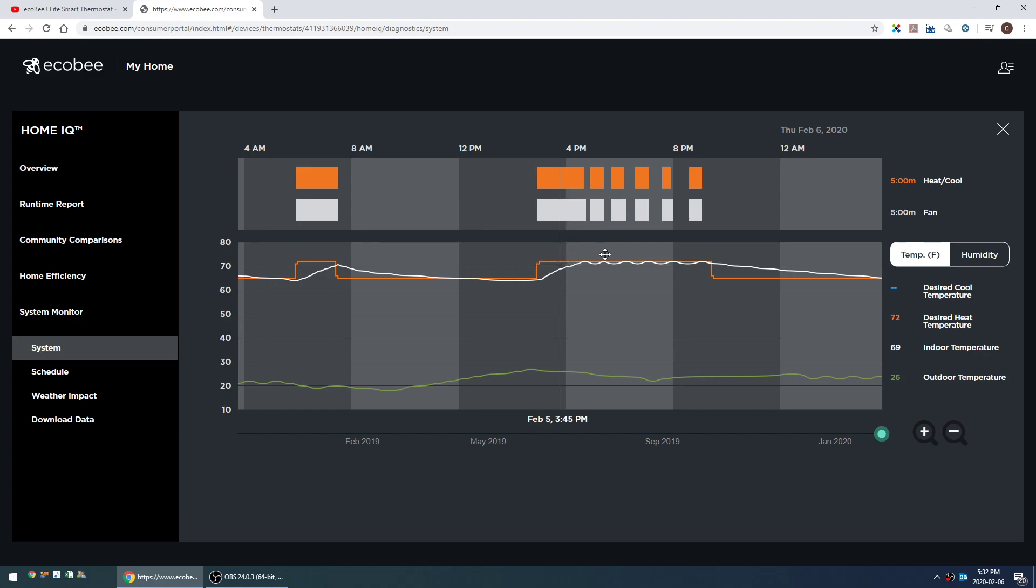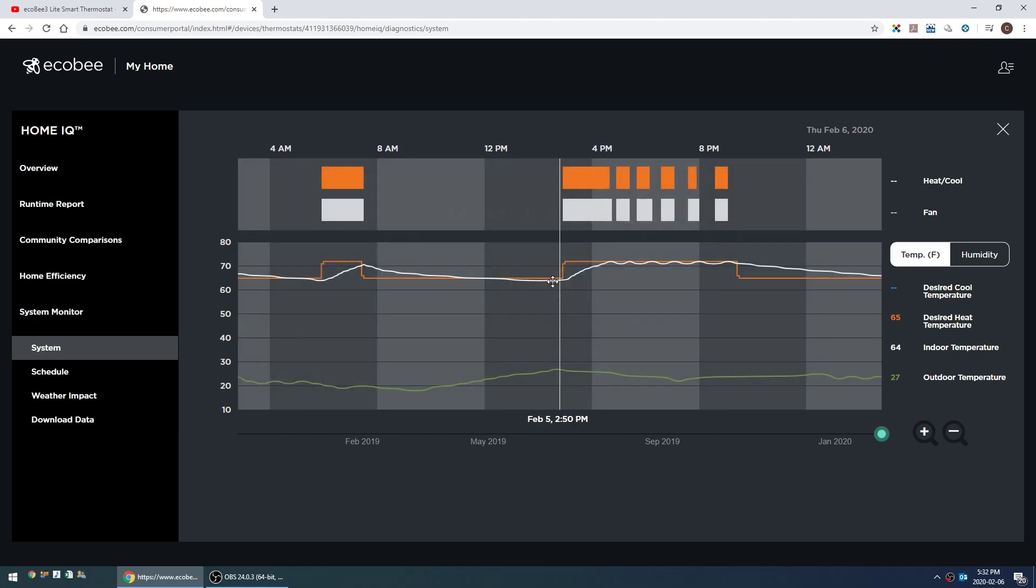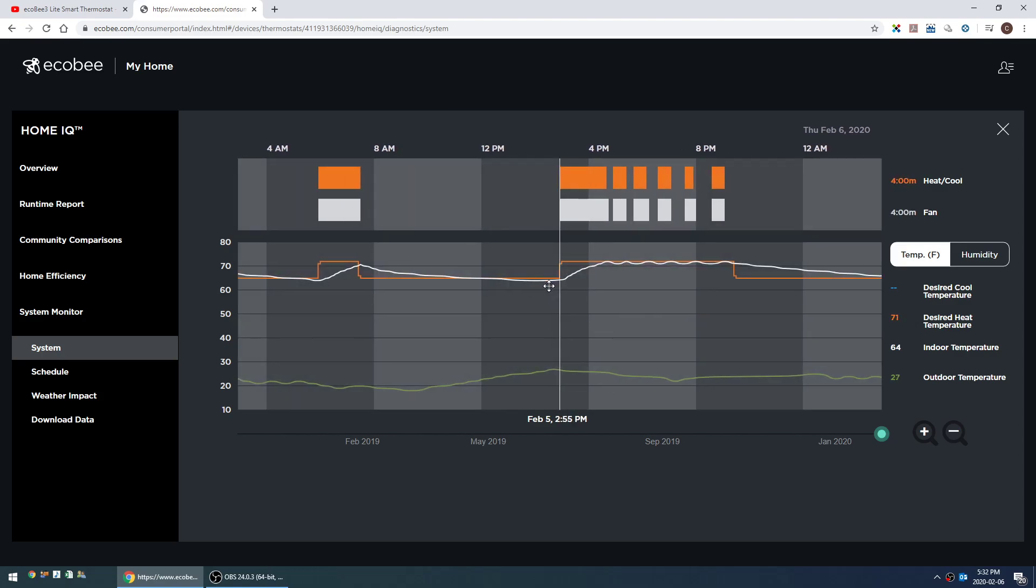This orange bar down here is the set point. We can see that right at three o'clock my set point goes from 65 degrees up to 72 degrees. The white line here is the actual inside temperature. You'll notice that the inside temperature actually got below the set point. I've set my threshold to allow the inside temperature to go a degree below my set point before the furnace kicks on. So that explains that. And then down here, this is the outdoor temperature. You can see how that fluctuates over time.